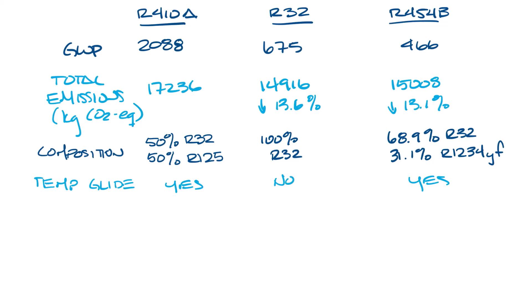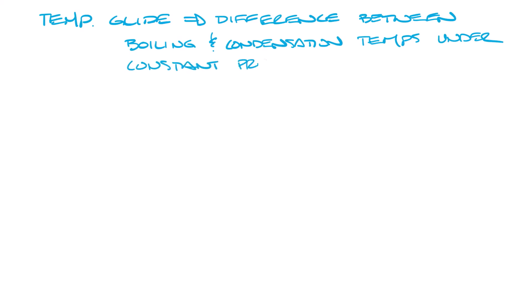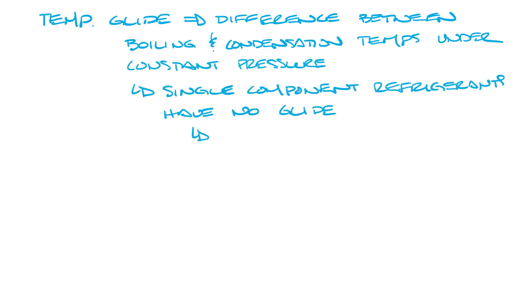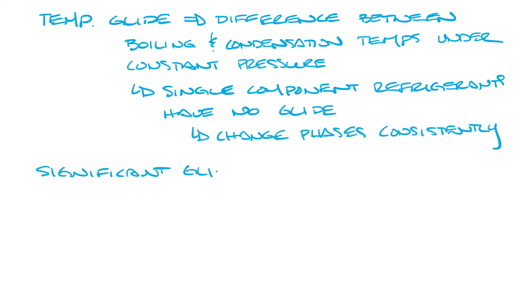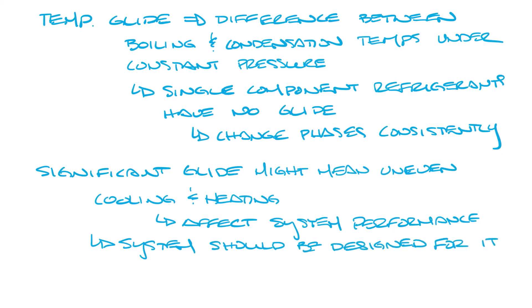So let's move this over and look at glide. Temperature glide is the difference between the boiling and condensation temperatures of a refrigerant when it's under constant pressure. Single component refrigerants have no glide. They change phases consistently. A significant temperature glide might mean that you have uneven cooling and heating, and this can affect your system performance. But the system should be designed to account for it.